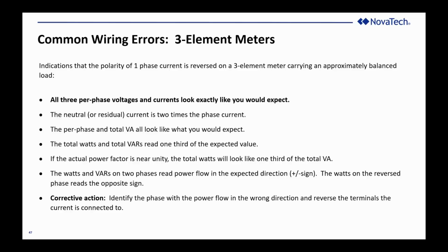The total watts and the total VARs read 1/3 of their expected value. Well, that's kind of intuitive because if I've inverted the polarity of one phase, then I've got 2 phases pointing in one direction, 1 phase pointing in the opposite direction. The 1 phase that's pointing in the wrong direction is going to cancel out one of the 2 phases that's pointed in the right direction. And what I'm left with is the 1 phase that's pointed in the right direction. So the total is going to be about 1/3 of what I expect.